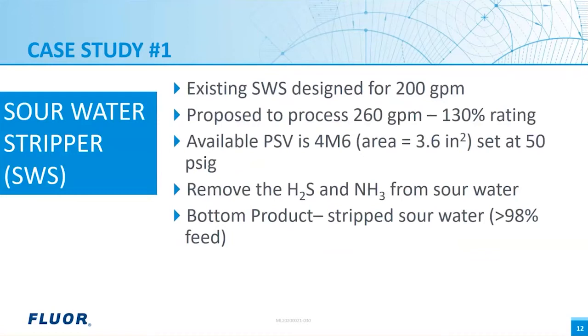Here is an example of dynamic simulation applications: relief analysis for a sour water stripper. This is a typical case for an existing column PSV re-rating with increased throughput. The column is designed to process 200 GPM sour water, now proposed to process 260 GPM, which is 130% of the original rating. An M-size PSV was installed with a set pressure of 50 psi. The column removes H2S and ammonia from sour water. The bottom product is the dominant part of the feed, taking above 98% of the feed, so the overhead is small — therefore the unbalanced heat method does not fit.